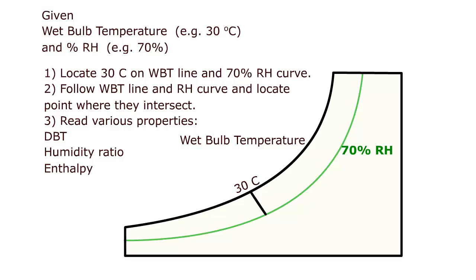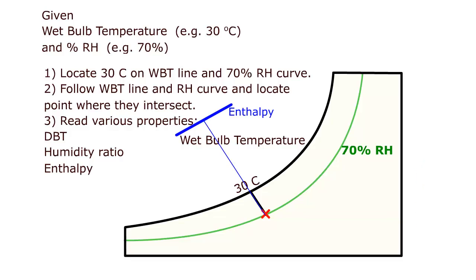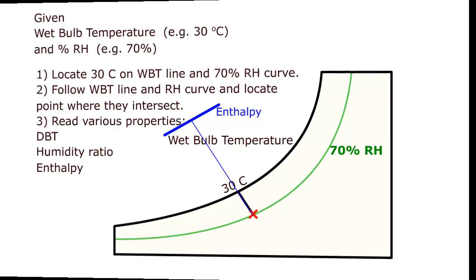Let's consider another example where the wet bulb temperature and percent relative humidity are given. Here, the wet bulb temperature is 30 degrees C and relative humidity is 70 percent. We follow the 30 degrees C wet bulb line and see where it meets the 70 percent relative humidity curve. From that point, we read the dry bulb temperature from the vertical line, the humidity ratio from the horizontal line, and the enthalpy from the constant enthalpy line.